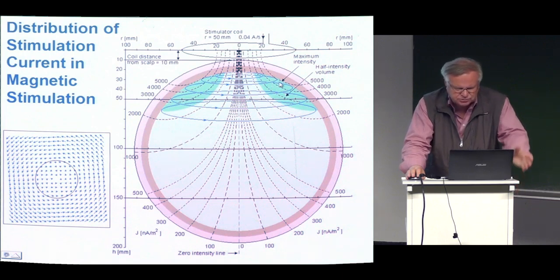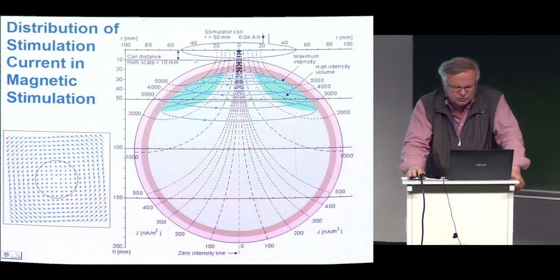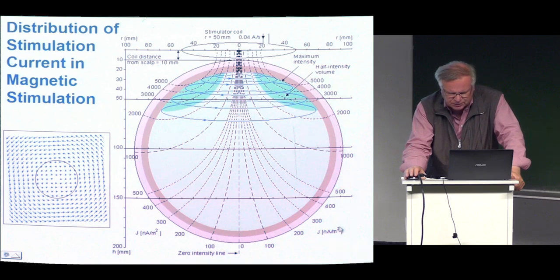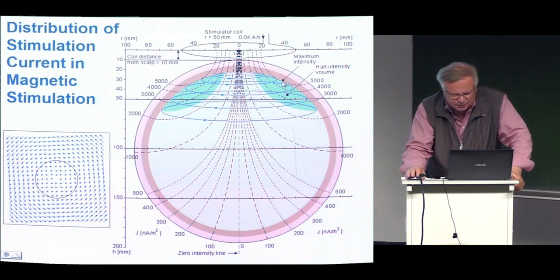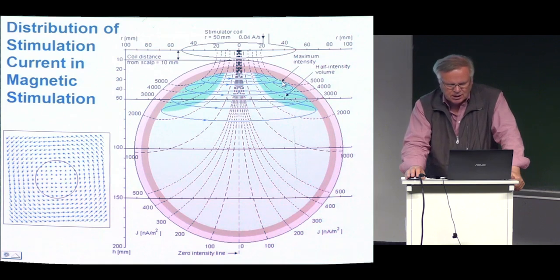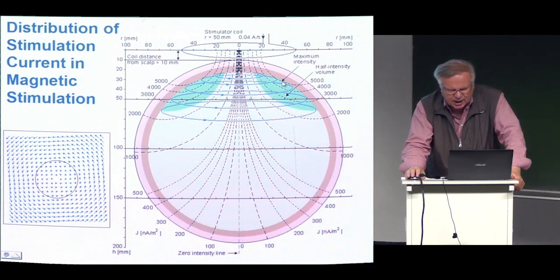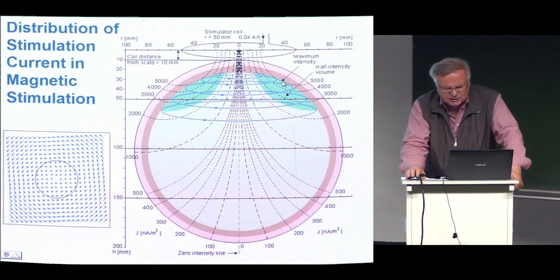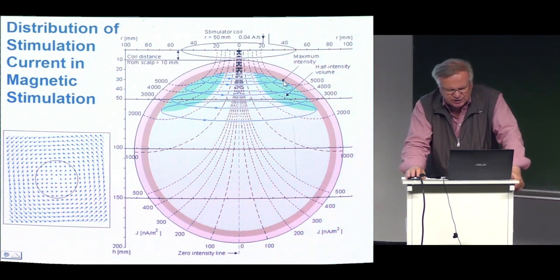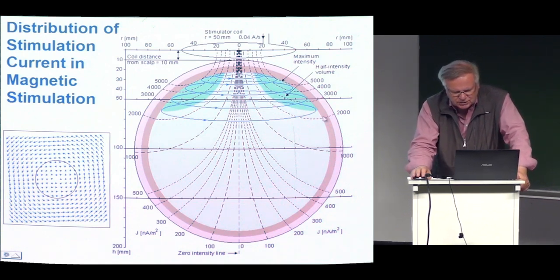With numbers: you select what is your current here in the coil and then you find what the current is here, in nanoamperes per square meter - that is the unit. If there is 0.04 amperes per second to this coil, it is 5,000. Then we find the iso-density surface where it is one half of that - it is 2500, it is here.